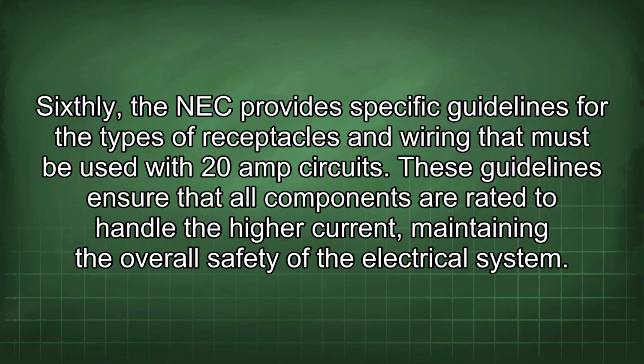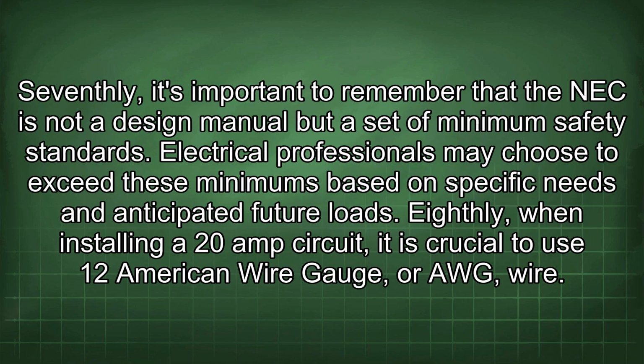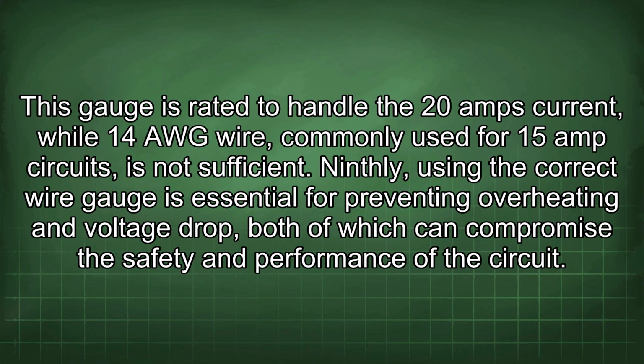These guidelines ensure that all components are rated to handle the higher current, maintaining the overall safety of the electrical system. Seventhly, it's important to remember that the NEC is not a design manual, but a set of minimum safety standards. Electrical professionals may choose to exceed these minimums based on specific needs and anticipated future loads. Eighthly, when installing a 20 amp circuit, it is crucial to use 12 American Wire Gauge, or AWG, wire. This gauge is rated to handle the 20 amp current, while 14 AWG wire, commonly used for 15 amp circuits, is not sufficient. Ninthly, using the correct wire gauge is essential for preventing overheating and voltage drop, both of which can compromise the safety and performance of the circuit.